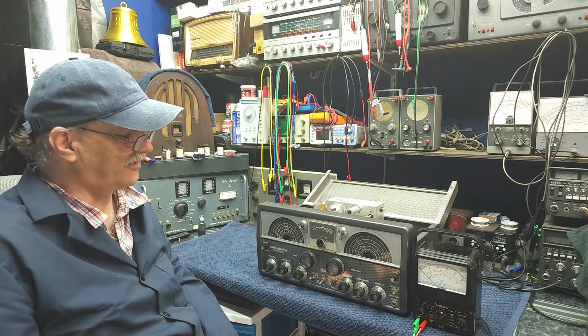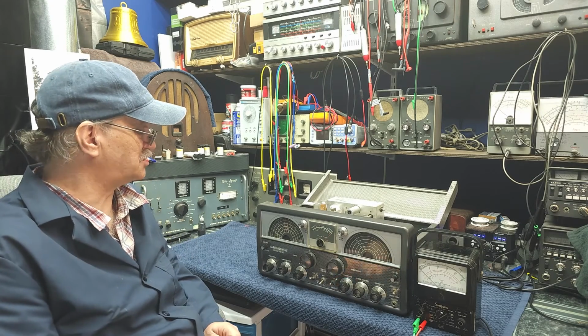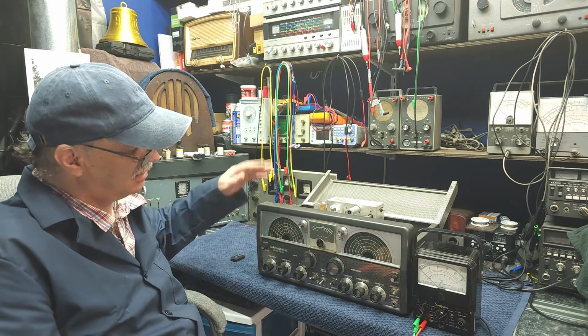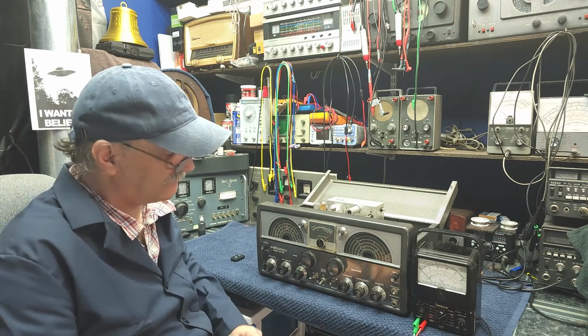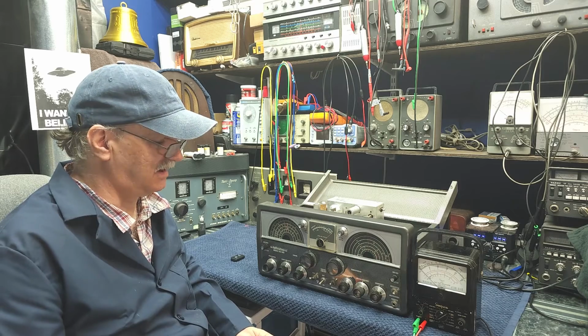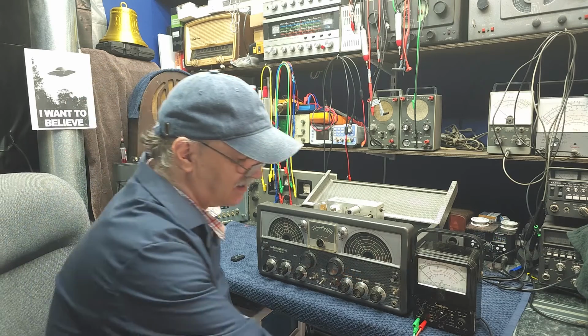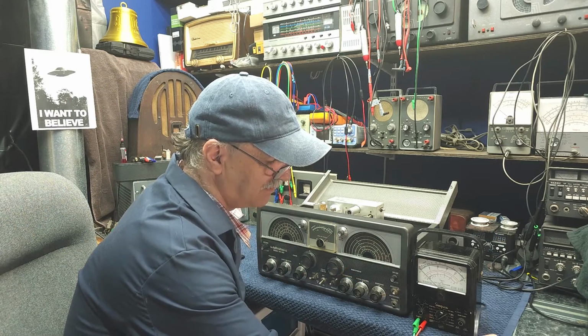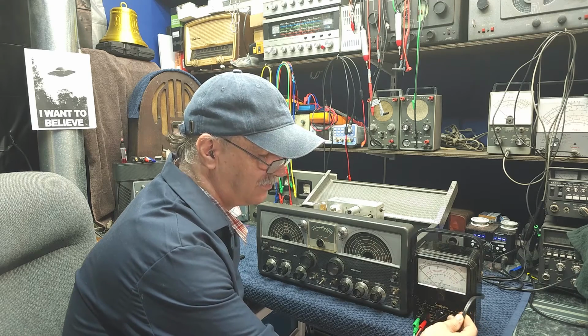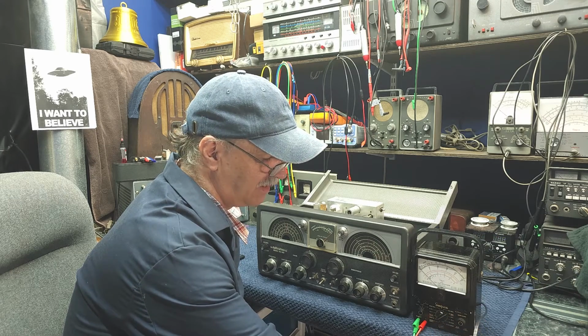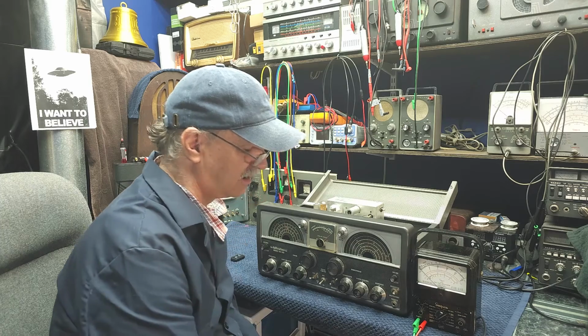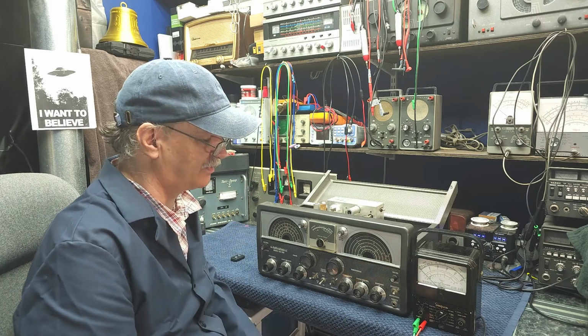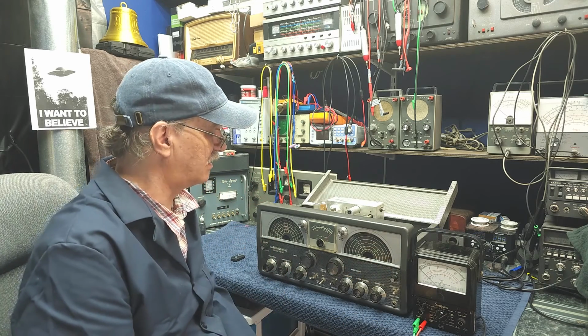Okay, let's verify the first customer's complaint about getting a shock on the outer case. Now, I'm questioning the restoration job that was done on it, as they did replace the line cord. They put a new line cord on, but it wasn't grounded. It's only a 2-wire cord into a hardware store type replacement polarized plug. We'll see how that's wired.